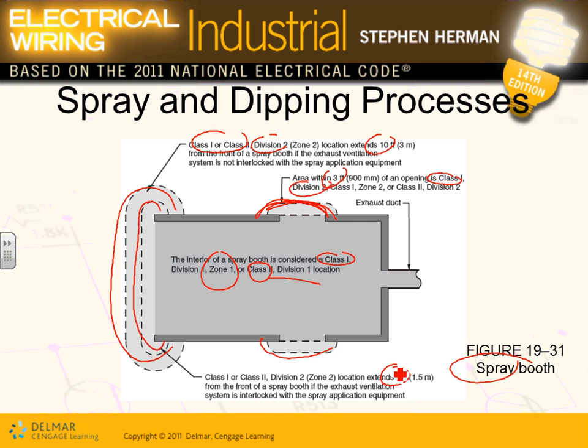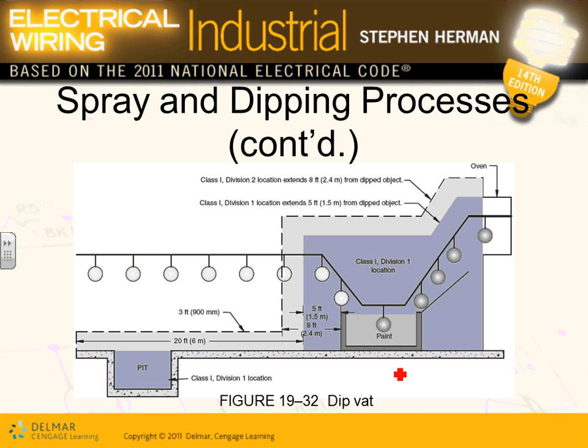Can you see 5 feet from every opening? Right here, up to 10 feet from the opening. And 3 feet from this one. Any comments, guys? Any questions? So you're going to avoid putting any electrical system in these areas, or if you put them, they have to be explosion-proof equipment, or dust ignition-proof equipment if it's dust. That's your spray area. Dipping area.